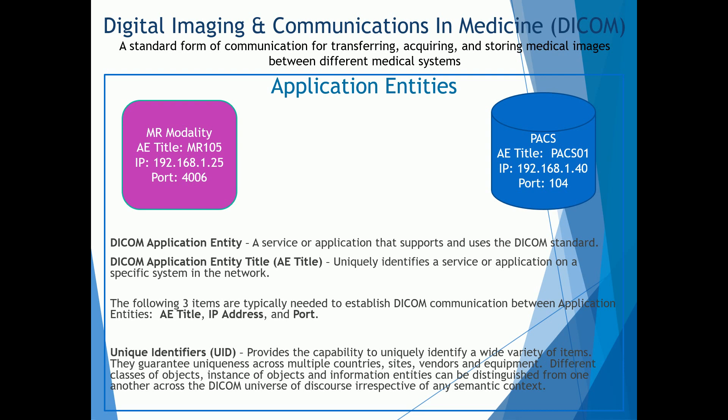The AE title, IP address, and port number are the three identifiable items that you need. Sometimes some may be optional depending on how your device is configured, but typically these are the items you need to communicate with another medical device.